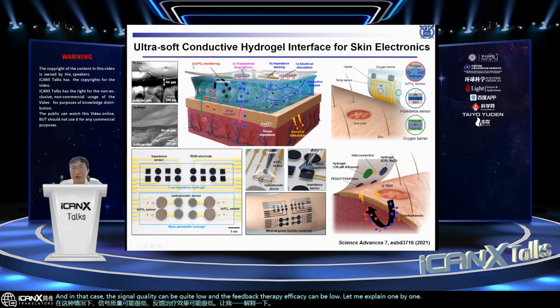For example, if we want to measure transcutaneous oxygen concentration, typically we apply heat using a heater here. Then by applying heat, oxygen molecules can be diffused out from the blood vessel, and transcutaneously they can be transported to the electrode, and we can electrochemically analyze local oxygen concentration. That's the concept. But if we have an air gap, then the extracted oxygen will be mixed with the external air, so significant error will be involved.